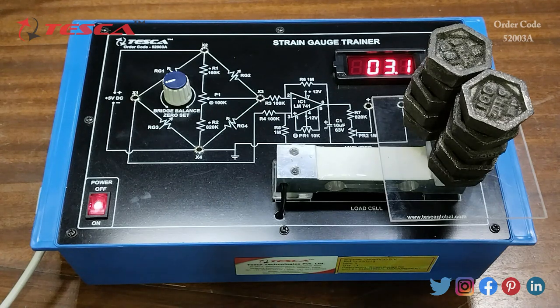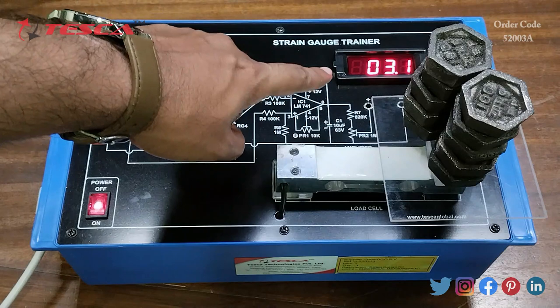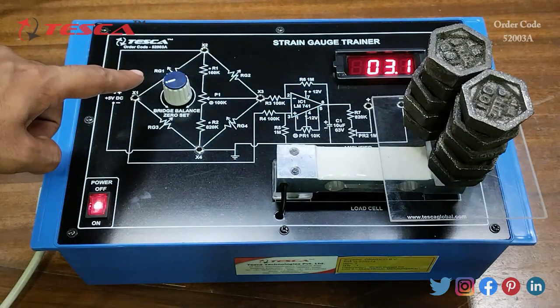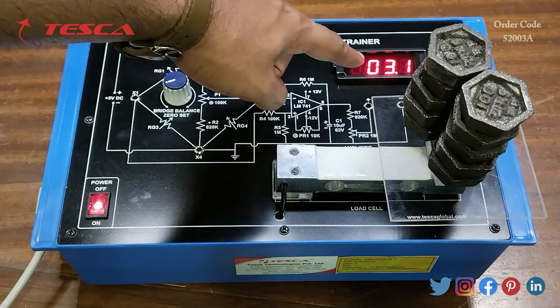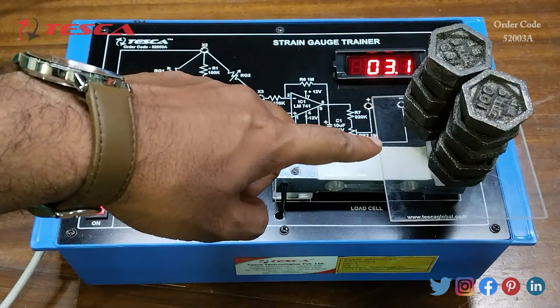We can also perform another experiment: to determine the linear range of operation of strain measurement. The procedure remains the same as the earlier experiment. When you switch on the kit, set the display reading to zero using the bridge balance zero set pot, and once the display shows 0.0, begin applying 100-gram weights one by one.